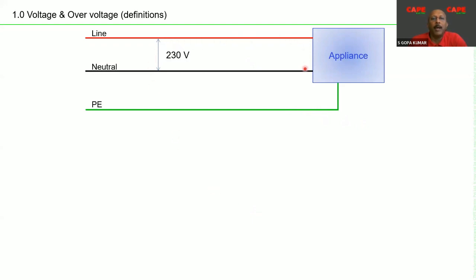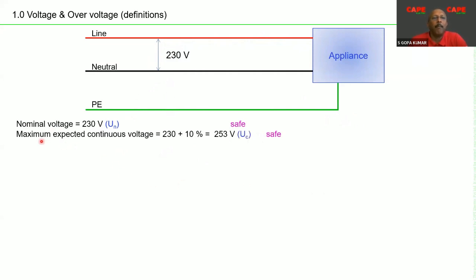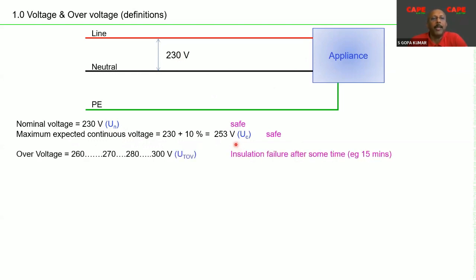So voltage and the voltage parameters are very important, the first important point to find out the performance of SPD and its application. So in the standard, the first one is nominal voltage. Nominal voltage is nothing but the normal voltage, 230 volt, for example. Under this condition, your appliance is 100% safe. Maximum expected voltage, you know very well that 230 plus or minus 10%, we say generally. So let us assume that plus 10%, this is the maximum voltage which can come between line to neutral, and under this condition your appliance must be safe.